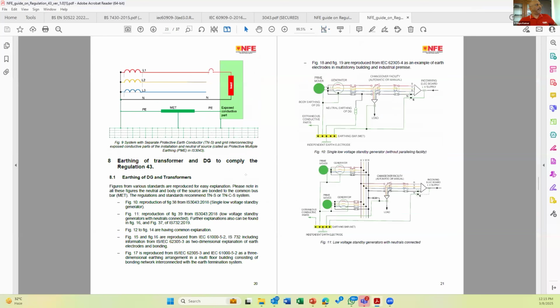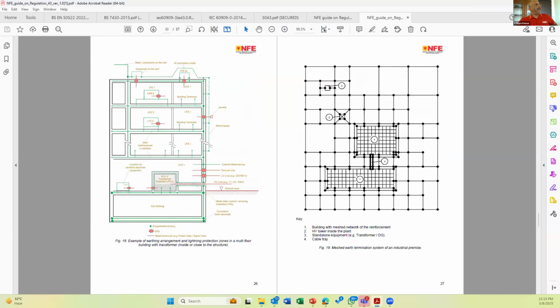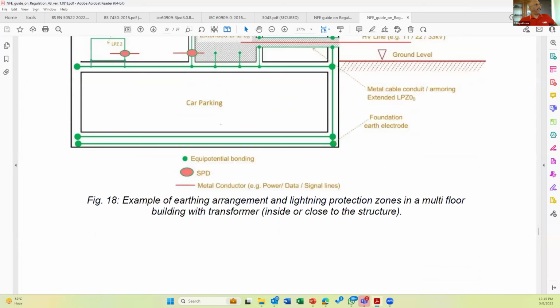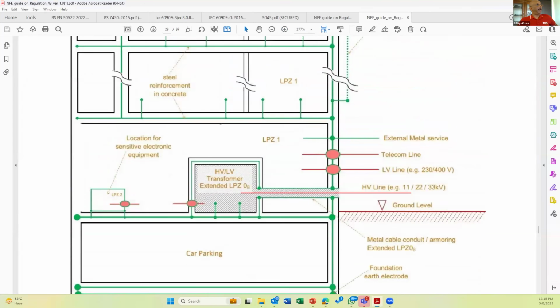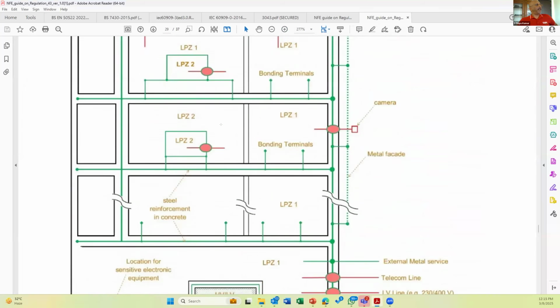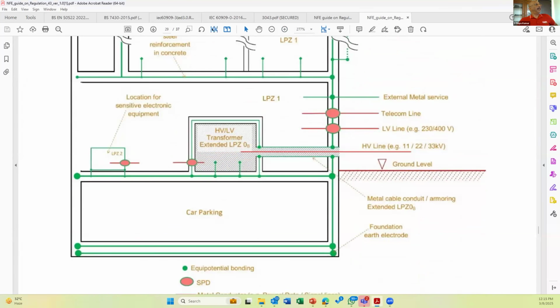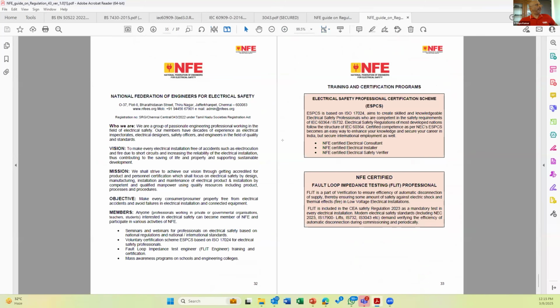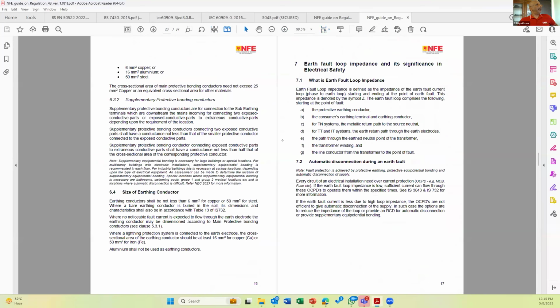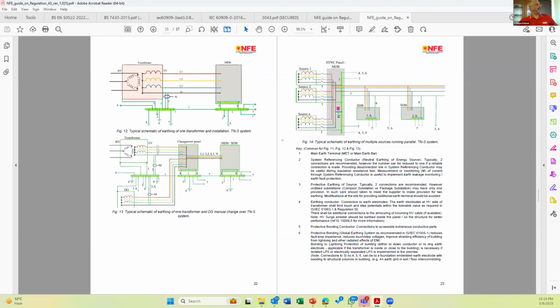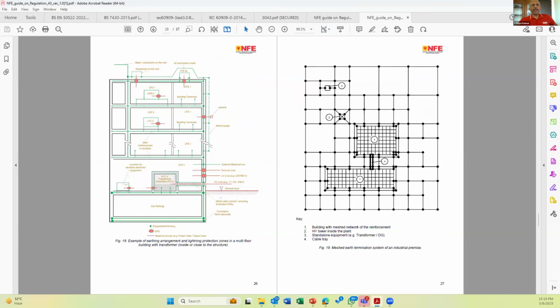In a residential building, how many earth electrodes are required? I would recommend the gentleman who has asked to go to the National Building Code of India. You download the National Building Code of India or IS 732, where you can find this particular picture, how to make earth electrode in a building. I think a better picture is also there. Both in NBC as well as IS 732, you can find this kind of a picture. So I would recommend you please go through, and for your question, how many earth electrodes, if you are asking about vertical rod or pipe, I would say 0. You don't need a pipe or a rod in a building. You can make use of the foundation steel, which is called foundation embedded earth electrode.